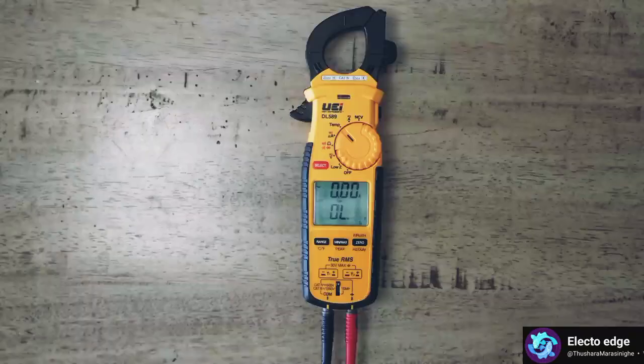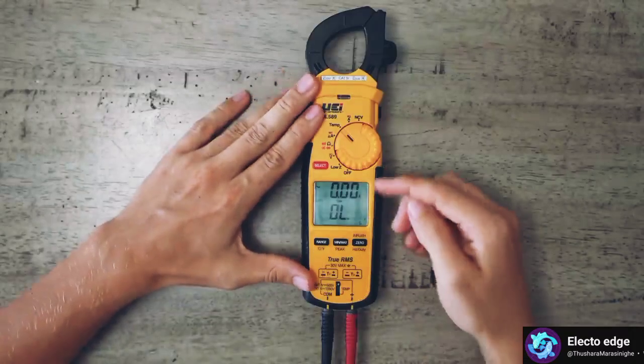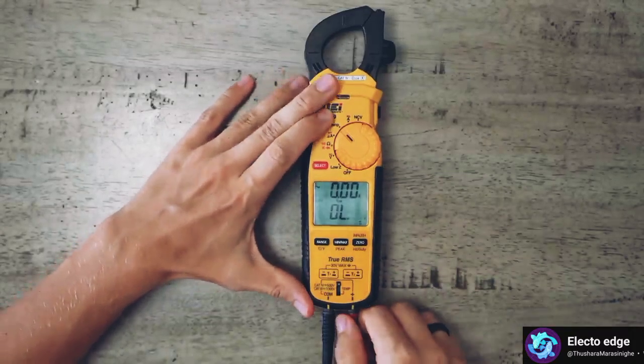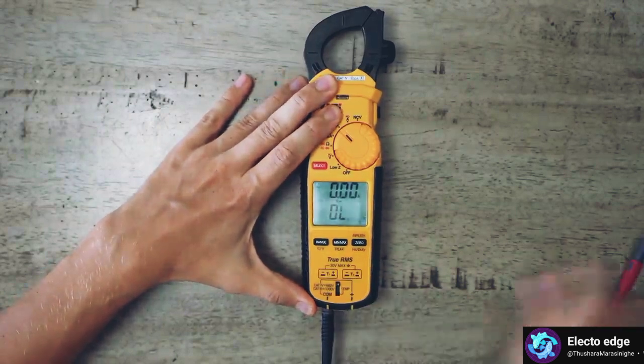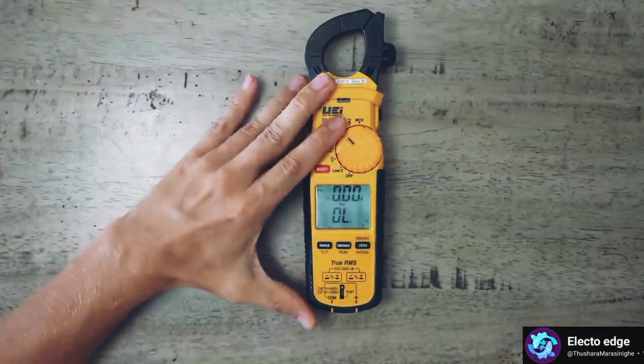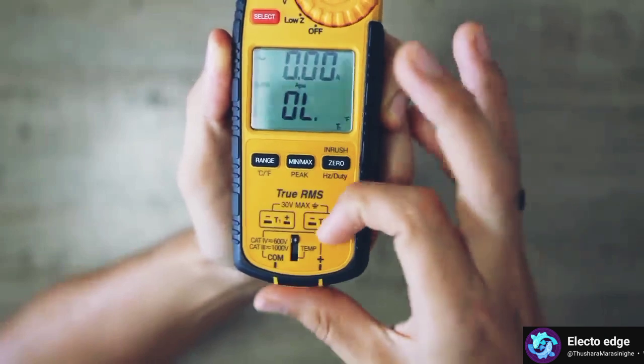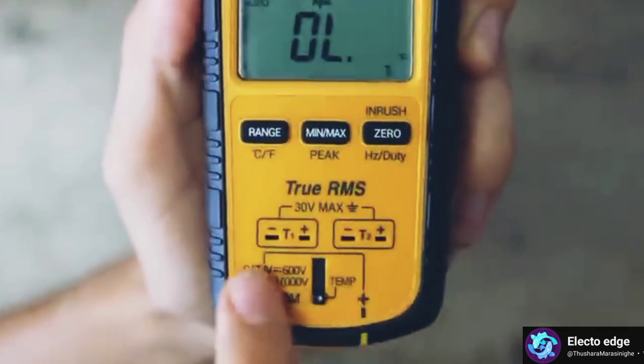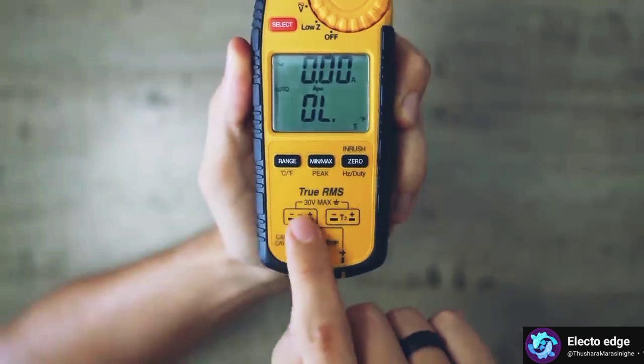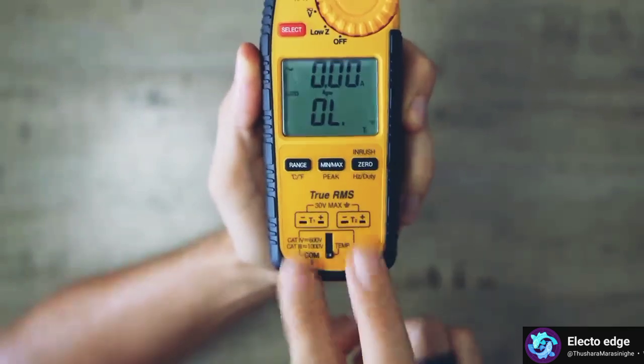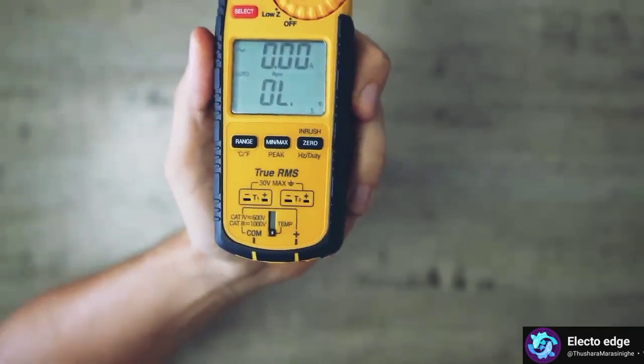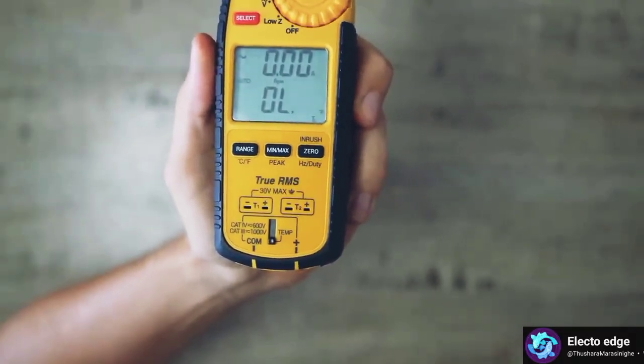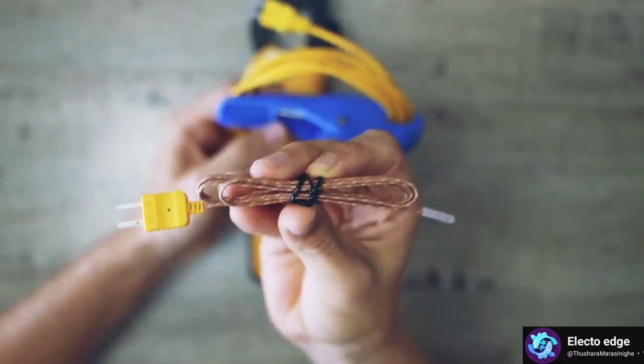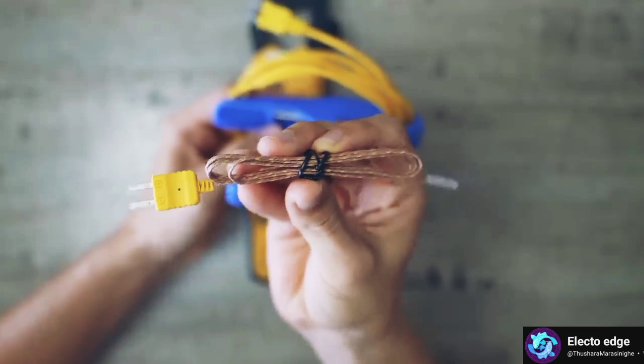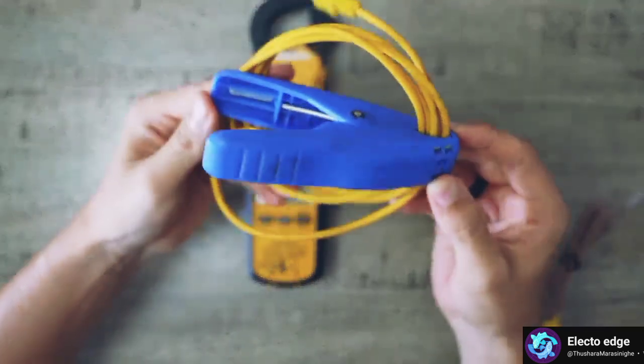If the diode is bad, then you would get a read on both ends or get no read on both ends. Next up is temperature, and if your meter has the temperature option, usually you have to disconnect the meter leads before you can plug in your probes. After the leads are disconnected, I move this little knob to temperature, and then I can plug my probes in. Most meters are only going to have one of these plugins. This meter has 2 of them, which is perfect to measure the temperature difference between 2 points, also known as the delta T. You can use a K-type temperature probe or a clamp-on temperature probe.